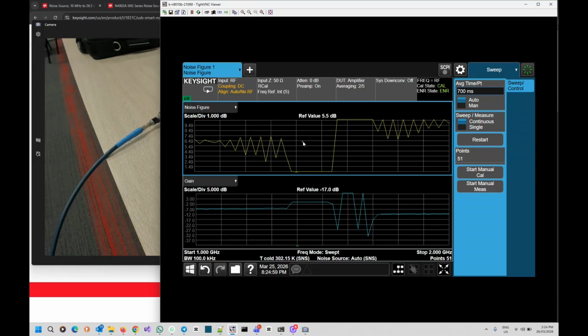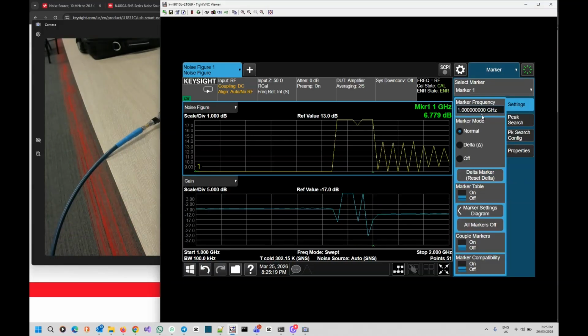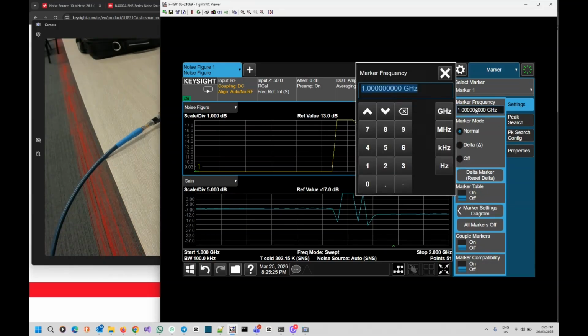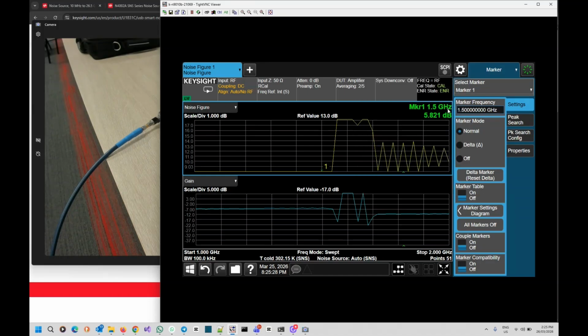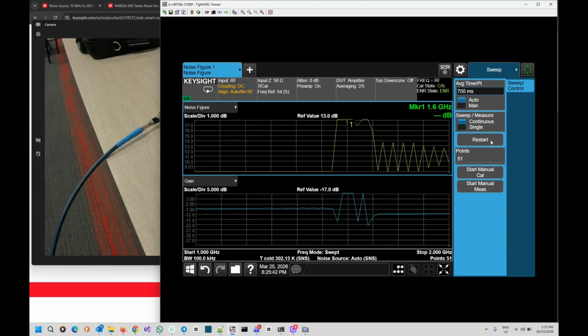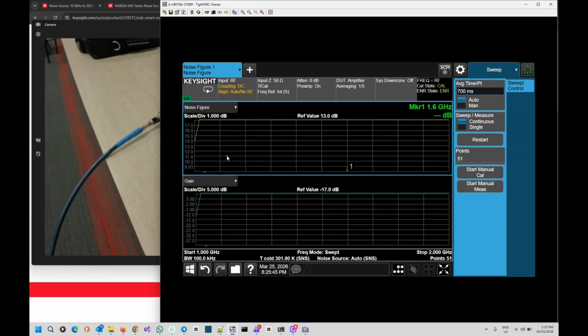So you can see that the reading is not that great. It just gives you an average reading right now, and this is the part where we left the cable open before the connection was done, and let it run for a while. It should continue to go down, and right now if you turn on the marker, it will be way above the value. The marker is over here, at about 1.5 gig. Infinity is a huge number, so it's not taking out anything. This is the reason why you need to restart your measurements so that it tallies with the current setup.